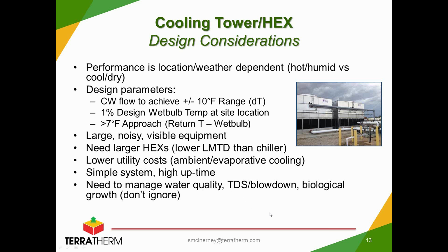They're simple to operate, high uptime, not a lot of complicated controls to shut the systems down. But the real trick with cooling towers, beyond just situating it and understanding the weather and how well you'll get the cooling that you're looking for, is that you need to manage water quality. Look at the quality of the water coming in, the fact that we're evaporating water to get the bulk of the cooling. Anything coming in terms of contaminant, total dissolved solids, particulate, that sort of thing, will tend to get concentrated over time. And you really need to be careful about setting the right blowdown and looking at issues like biological growth. These can be large bioreactors at times, possibly needing to add biocide and other additives to make sure that the water quality is there and doesn't impact your process systems.